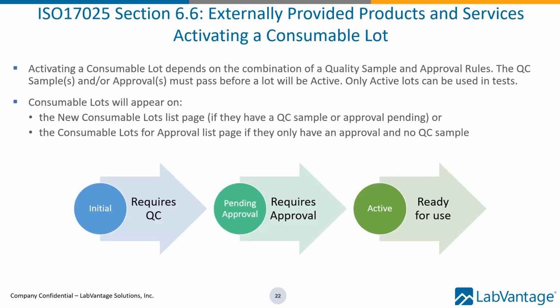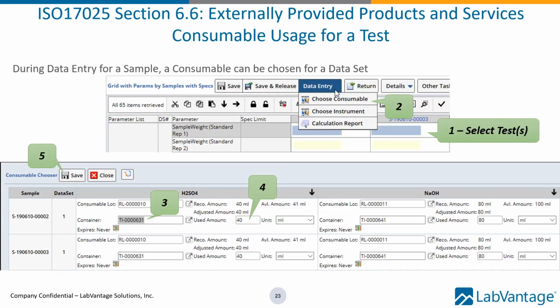So you can use your LIMS to set rules around what's required for each material type, and it can track the newly received or created lots and then queue them up for further testing and approval prior to being put into casework. These images really help illustrate the value of having your quality management system as an integral part of your laboratory information management system. When conducting an analysis on a piece of evidence, the ability to link the required consumables and instruments to that analysis enables the user to choose the specific lot numbers or the specific piece of equipment at the time they're doing the test.